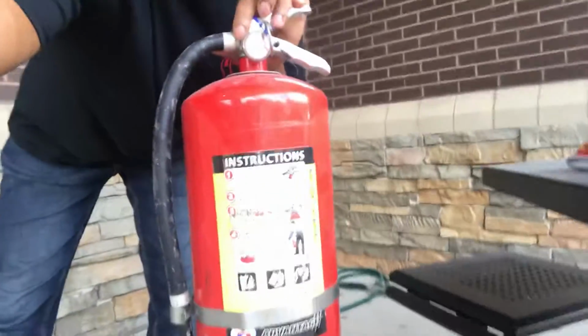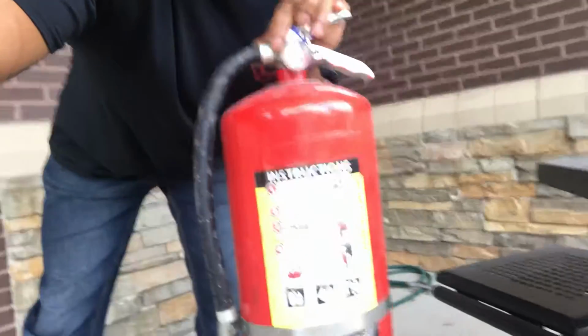The first one we'll be talking about is Class A fires, which are ordinary combustibles. They are solid combustibles that you normally see every day. For example, they could be cloth, cardboard, wood, plastic, and anything including trash. The best way to extinguish it is either water or a type ABC dry chem extinguisher.